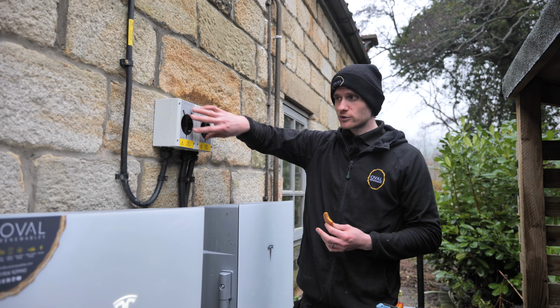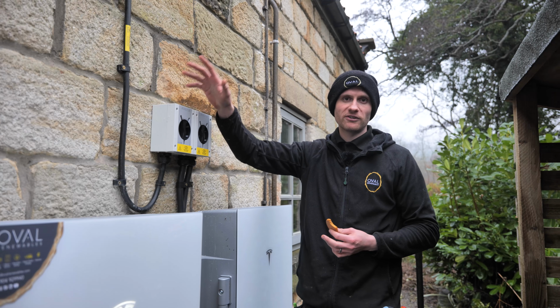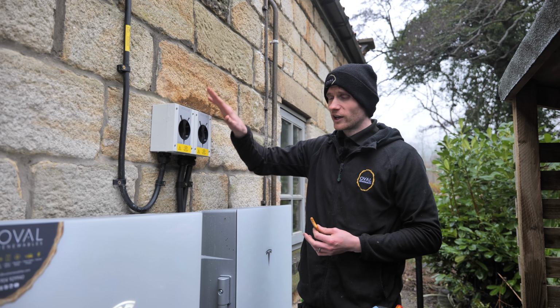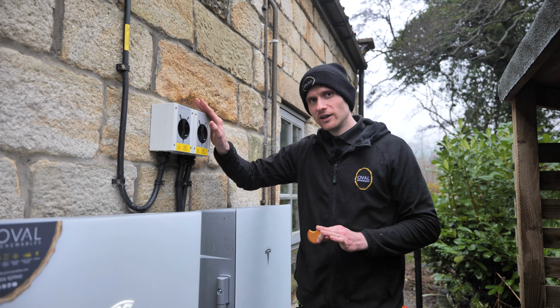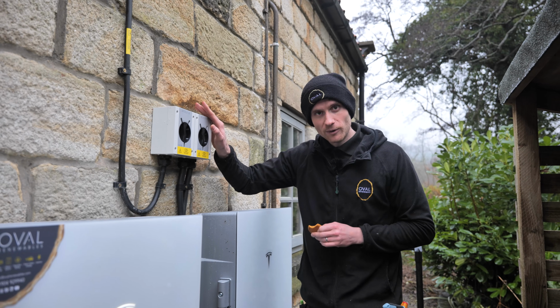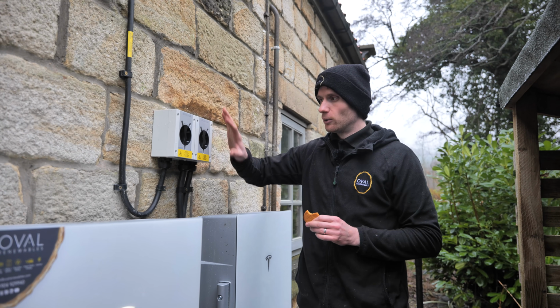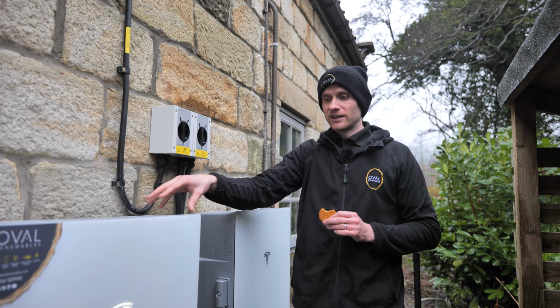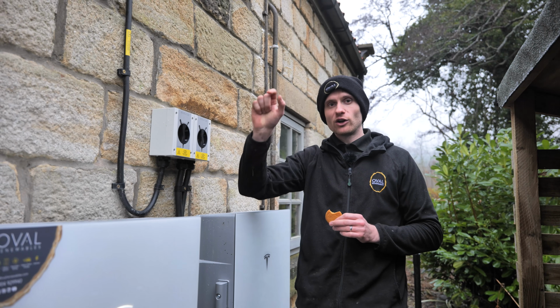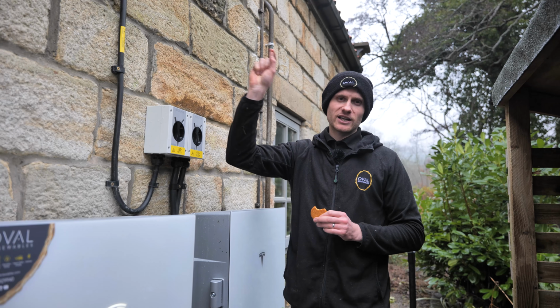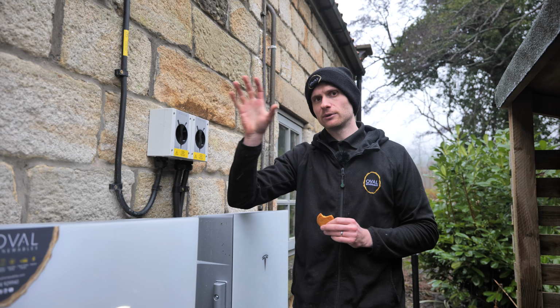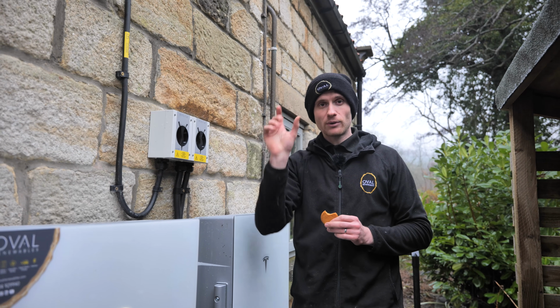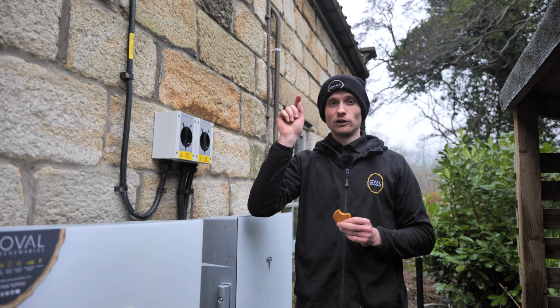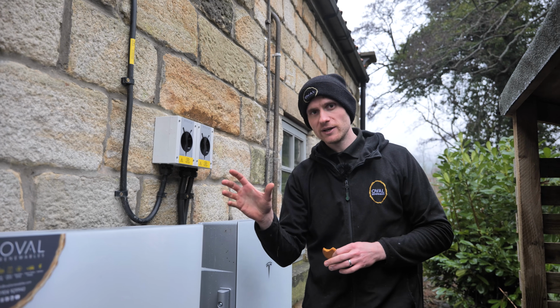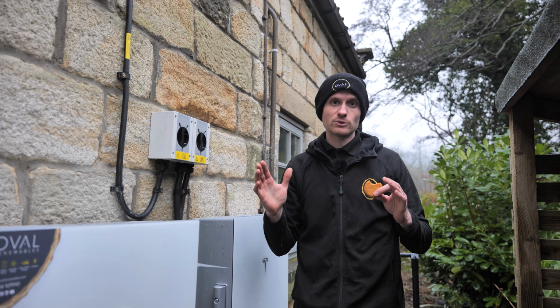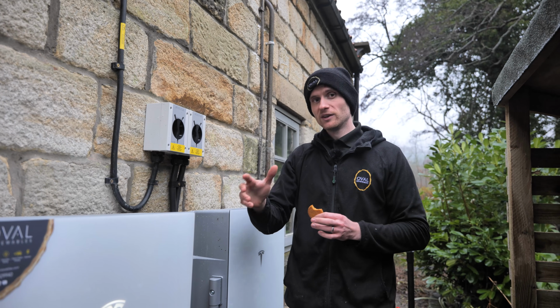Got 2 strings of solar panels, one on the house, which is 10 455 watt panels. We've then got a second string on some solar trackers, which are 6 400 watt panels, which is 2.4 kilowatts. Both of those go into the Powerwall 3 and are on separate MPPTs. We've then got a main 16mm armoured cable that runs through the house to hide that cable as much as possible and pops out into the brand new Proteus distribution board via a local AC isolator in there and generation meter. We've got that brand new Proteus distribution board where we've done a full test of the property.